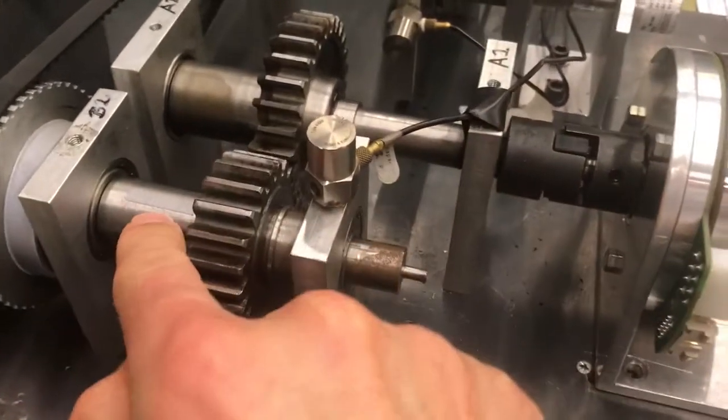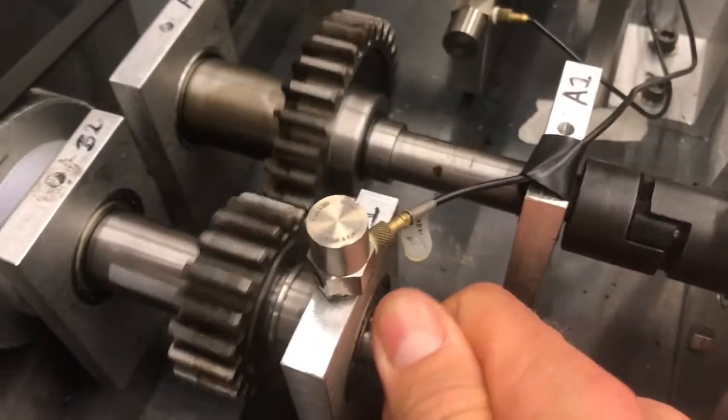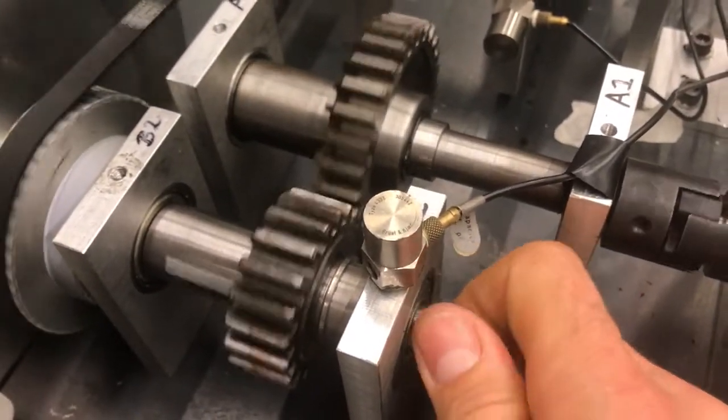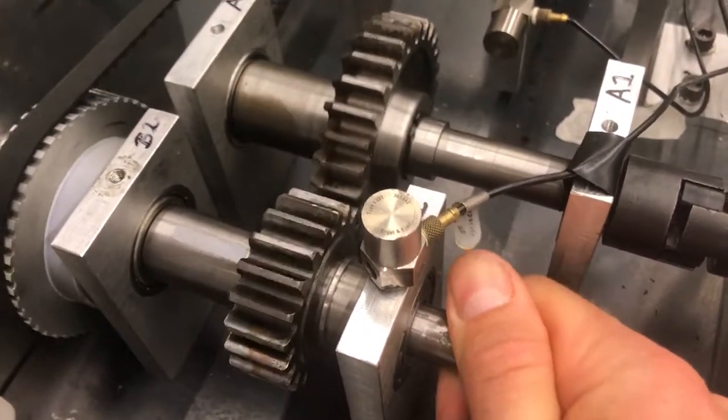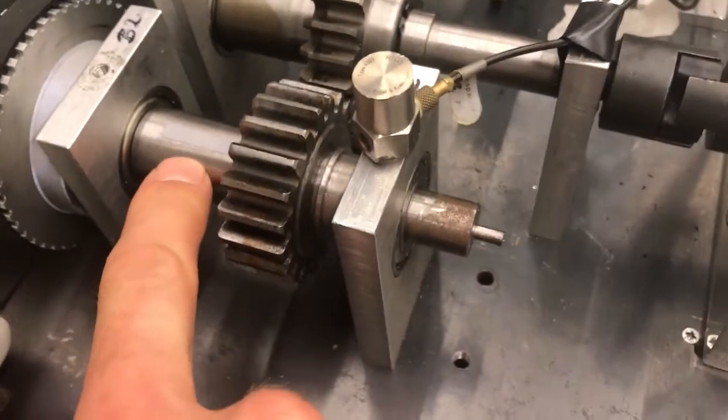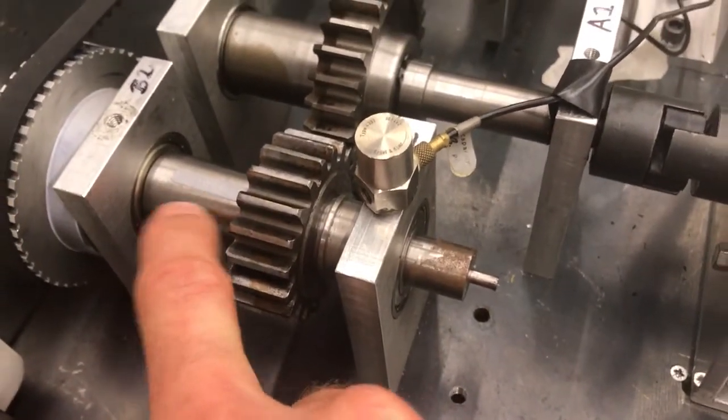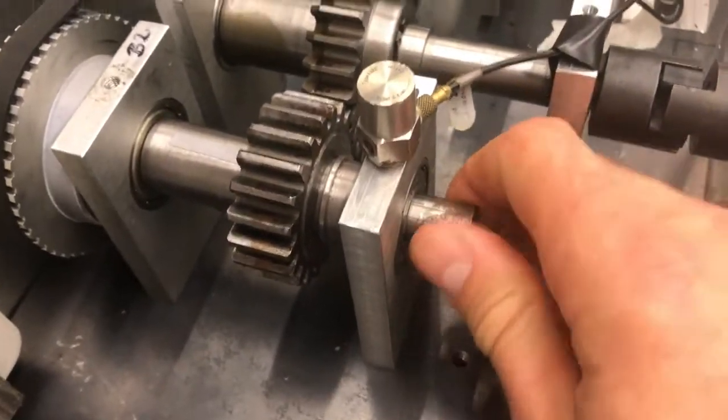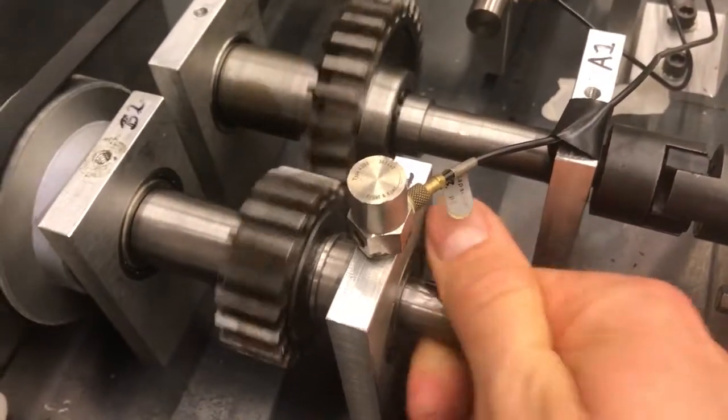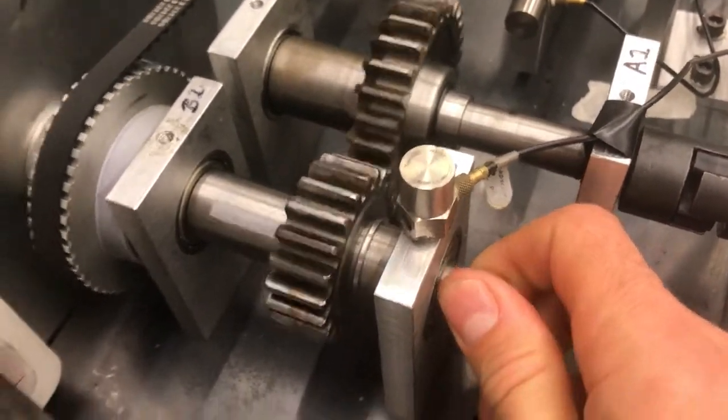There's a piece of retroreflective tape on this shaft here which you can see as I rotate the shaft comes around and that enables us to make a once per revolution tachometer measurement. Every time this tape passes by we have a signal comes back effectively a square wave and we can use that to determine the RPM of the shaft.